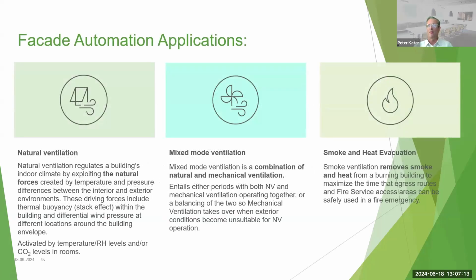So there are three basic categories of applications for facade automation. The first being natural ventilation. Natural ventilation regulates the indoor climate of a building, and it uses the natural forces created by temperature and pressure differences between the inside and the outside environments. And these driving forces include primarily thermal buoyancy, or the stack effect, and also differential wind pressure at different locations around the building envelope. The system can be also activated by inputs from temperature and humidity sensors and CO2 level sensors within rooms to optimize the indoor air quality.